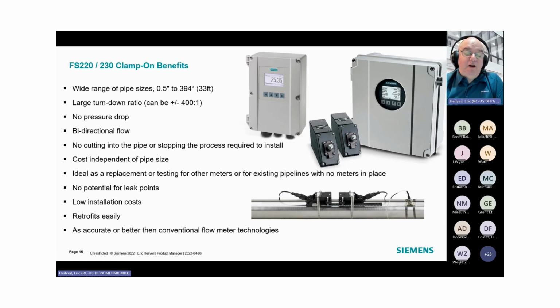The system that we have available allows us to mount the transducers and the bulk of the electronics right next to the pipe in a Class 1 Division 1 approved area, and then run a digital cable hundreds, 300, 400, 500 feet away directly into the transmitter. And that's called a DSL, or a digital sensor link. There is a built-in DSL in every single one of these units, but if we pull the DSL out and mount it on a standpipe, these transducers can have a cable 65 feet or 5 feet. And then you can go 300, 400 feet away into the transmitter with the SSL cable, or the digital signal cable.